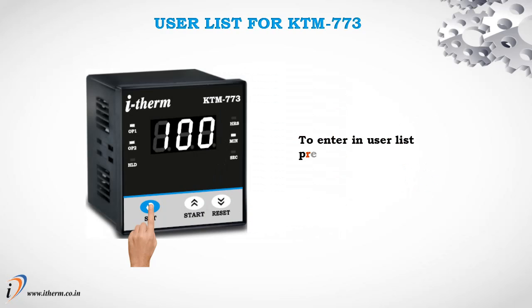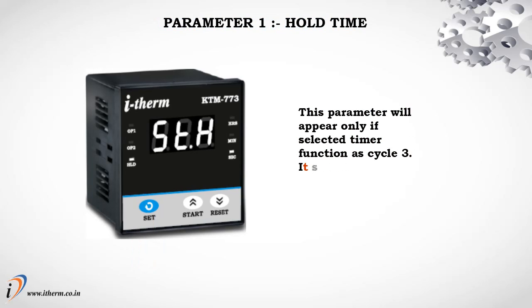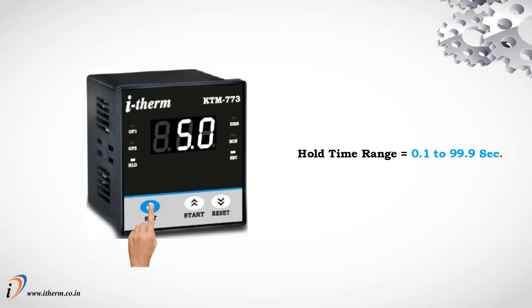User list for KTM-773. To enter the user list, press and release the set key once. Parameter 1: Hold Time. This parameter will appear only if the selected timer function is cycle 3. It sets the hold time between output 1 and output 2 in cycle 3. Hold time range: 0.1 to 99.9 seconds.